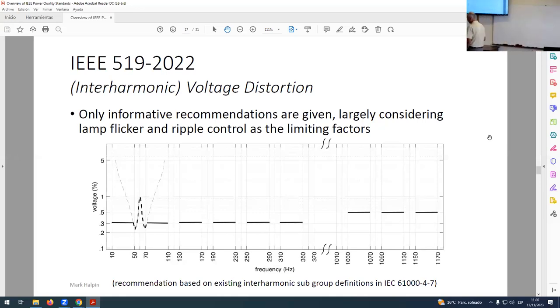But we are beginning to propose interharmonic voltage limits. Right now, interharmonic limits in lower frequencies are based on flicker, incandescent lamp flicker, right? But what about higher frequencies? Well, higher frequency disturbances don't cause an incandescent lamp to flicker. It does, but our eyes can't see it, okay? So in effect, it does. But does that mean that at higher frequencies, interharmonics don't need limiting?